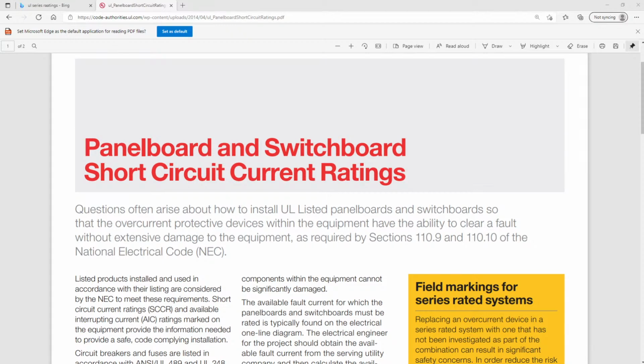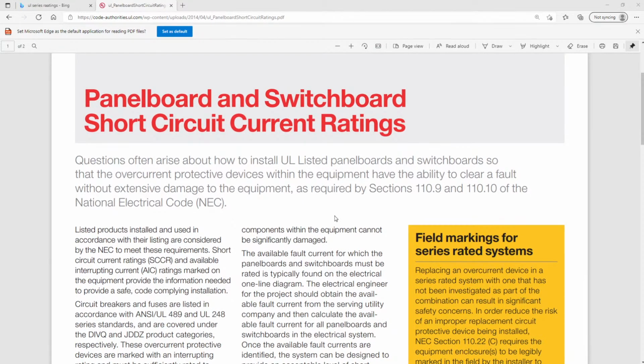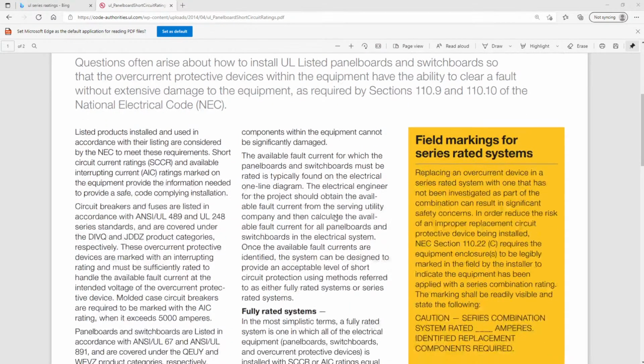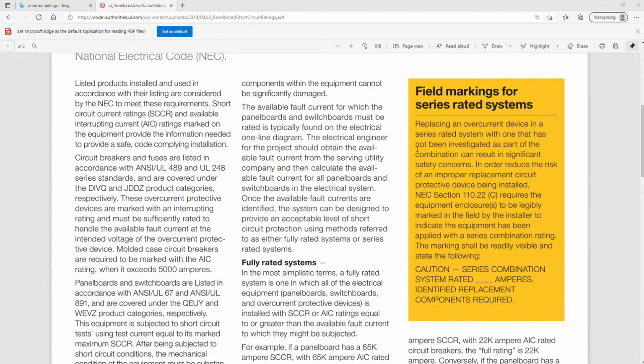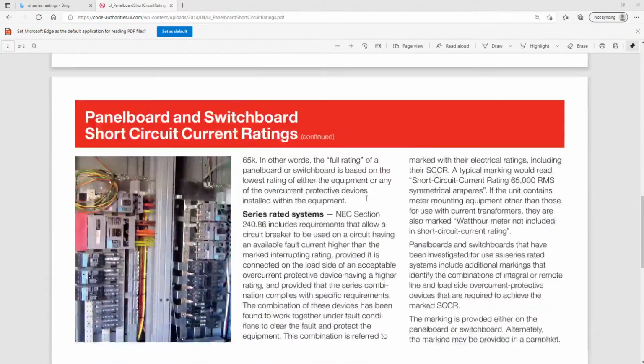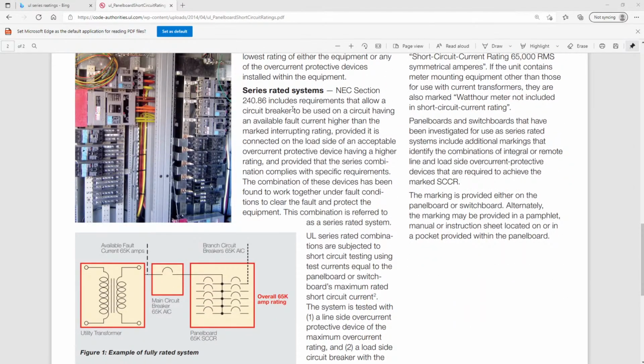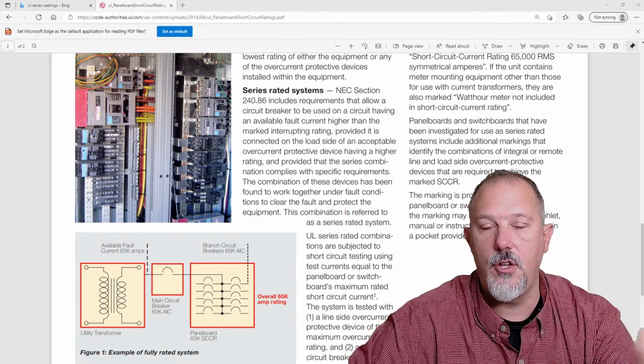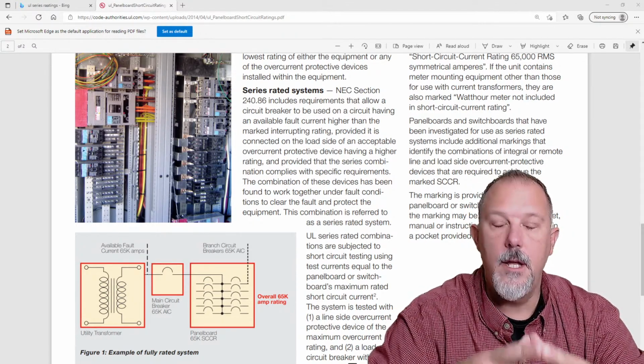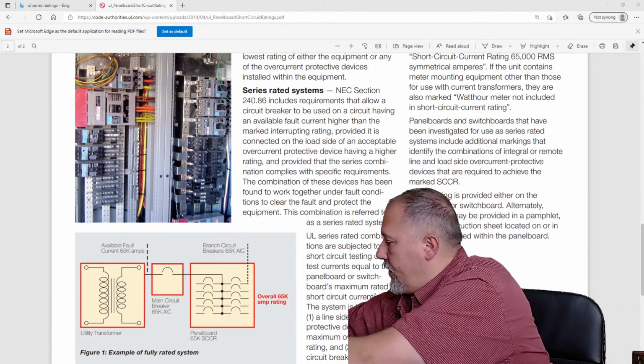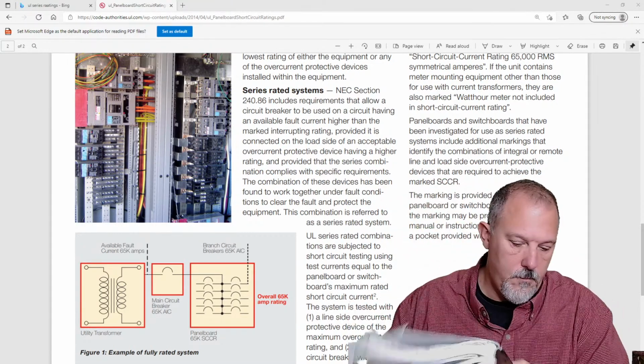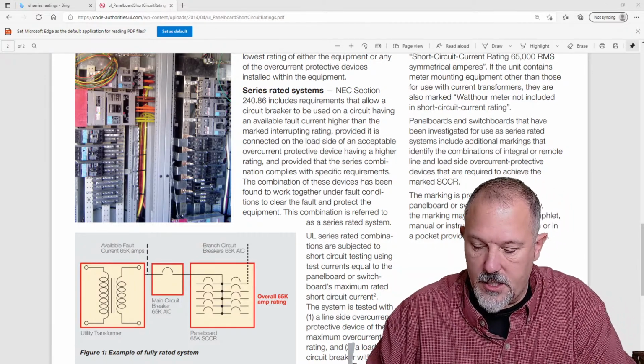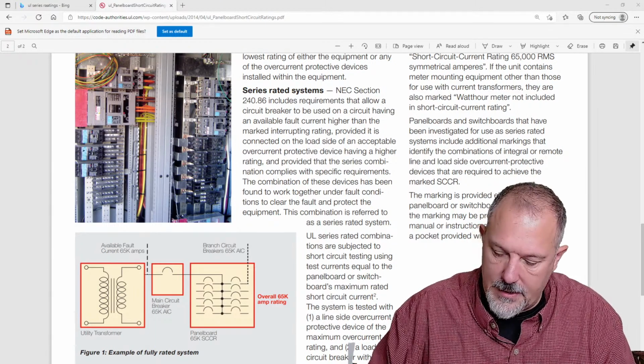This is a document published by UL that talks about panel board and switchboard short circuit current ratings. We'll talk about field marked, replacing an overcurrent device. We talk about fully rated systems and series rated systems, which is 240.86. And when you talk about using the up, over, and down method, you're trying to engineer a series rating. So let's just take a look at 240.86.